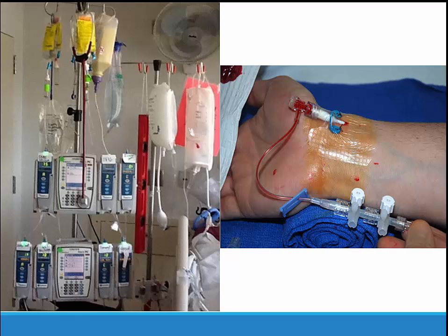If you look at this picture on the right, the cannula shown entering the radial artery is connected via pressure, non-distensible tubing to a transducer. The transducer converts the pressure wave into an electrical signal. The transducer is wired to an electrical monitoring system which amplifies the signal and displays and records it. Stopcocks are inserted into the line for specimen withdrawal and for referencing and zero balancing procedures.